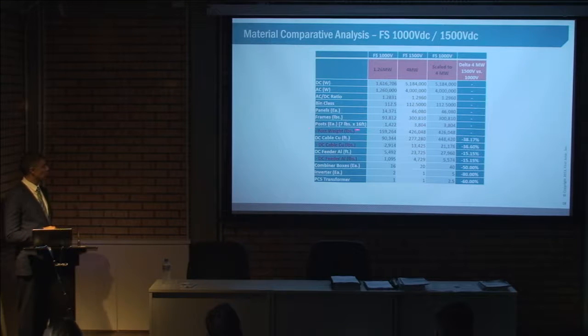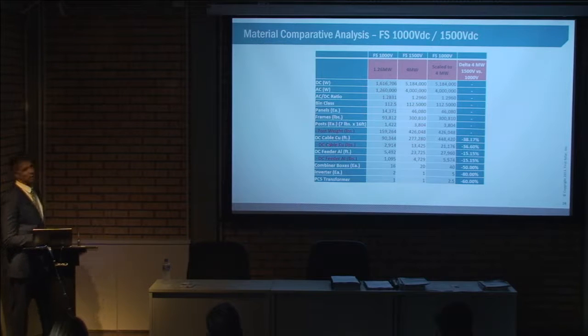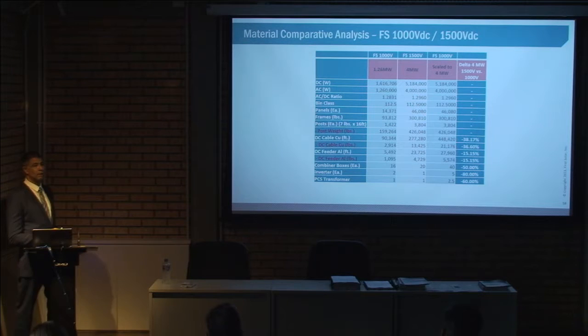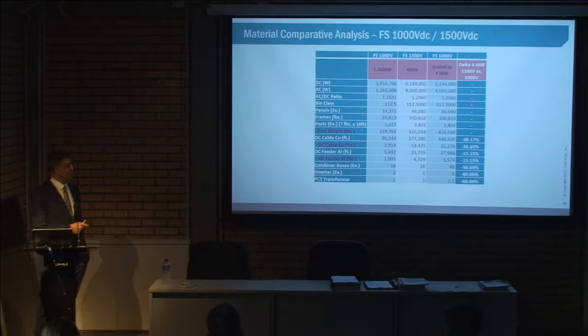All these components — hardware, mounting, the modules, the tracker structure — won't change whether you go to 1,000 volts or 1,500 volts. What changes is your cable, for example, the DC cables used for connecting the strings between modules, and then from the modules to the combiner boxes.